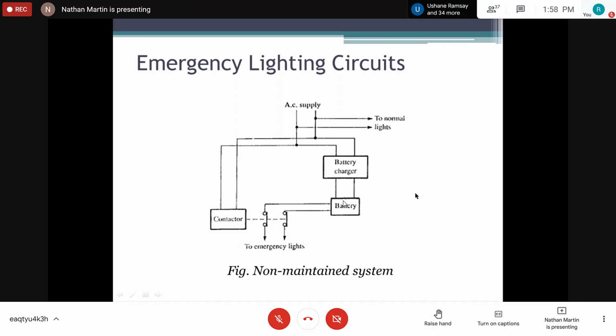However, in this non-maintained system, it's always good. There's always a test button on it for persons who are familiar with this type of device to test to see if the battery is actually operating, right? So what happens when you press the test device, it actually breaks one of the lines here and it will now be supplied from the battery in its normally closed position.